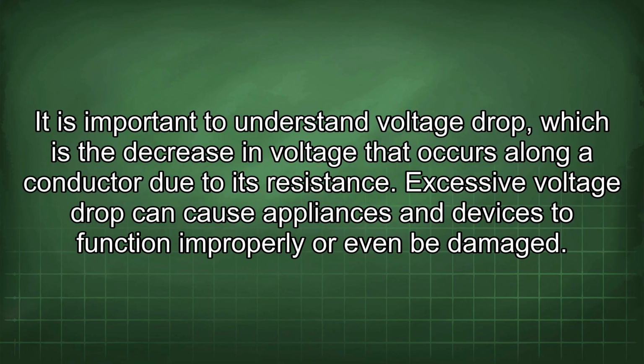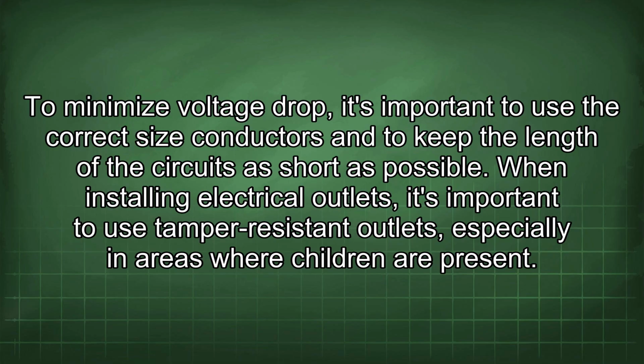It is important to understand voltage drop, which is the decrease in voltage that occurs along a conductor due to its resistance. Excessive voltage drop can cause appliances and devices to function improperly or even be damaged. To minimize voltage drop, it's important to use the correct size conductors and to keep the length of the circuits as short as possible.